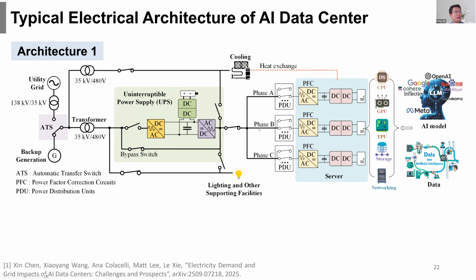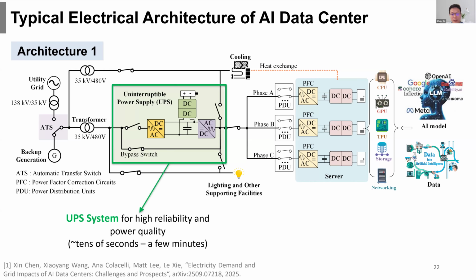You can look from the left to the right. First is connecting with the utility grid through the automatic transfer switch, and we also have the backup generation. Then it goes through a step-down transformer to lower the voltage. It's connecting with the UPS system. The UPS system is essentially the battery system. When there is a disturbance from the grid end, the computing load will be transferred to the UPS system immediately. Then it can last for tens of seconds or a few minutes before the backup generation picks up the load. In addition, we have this bypass switch. If the grid is in normal condition, the power can just go through the bypass switch and supply the computing load parts.